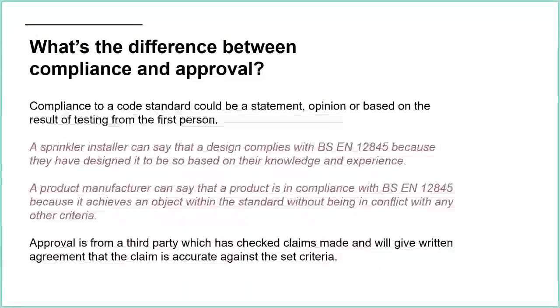ZoneCheck is not in conflict with any of the criteria within 12845, and it achieves one of the objectives, which is the testing of flow switches under certain flow conditions, for example. So it does that, it's not in conflict with the other 99% of the standard, and therefore we say, yeah, it is compliant. But it's just a little bit more complicated than some people realise.